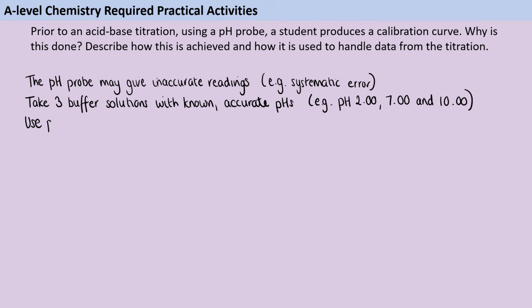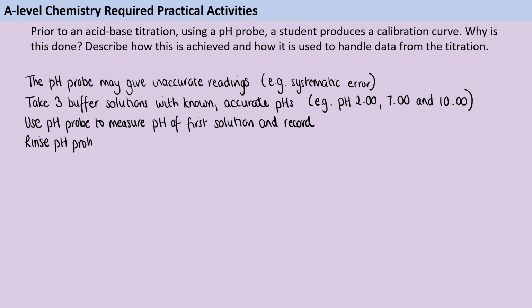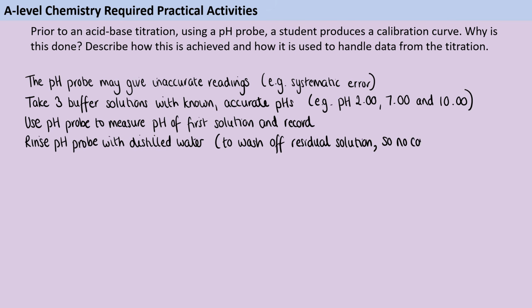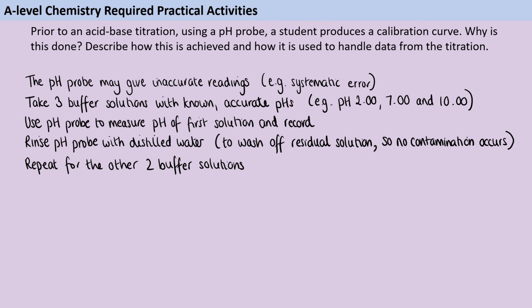So all you're going to do is take your pH probe and use it to measure the pH of the first solution and record that, and then you rinse it off with distilled water. The reason you're doing this is because you want to avoid contamination, you want to avoid there being residual solution left on the pH probe and that contaminating your next reading. So you give it a good rinse in between times, and then you measure your second solution and rinse it off with distilled water, and then you measure your third solution and rinse it off with distilled water before you put it back in the storage buffer if it has one. So now you've got 3 sets of data. You've got the actual pH that you know that this solution is, and then the pH that your pH probe says that it is, and you've got those for all 3 solutions.